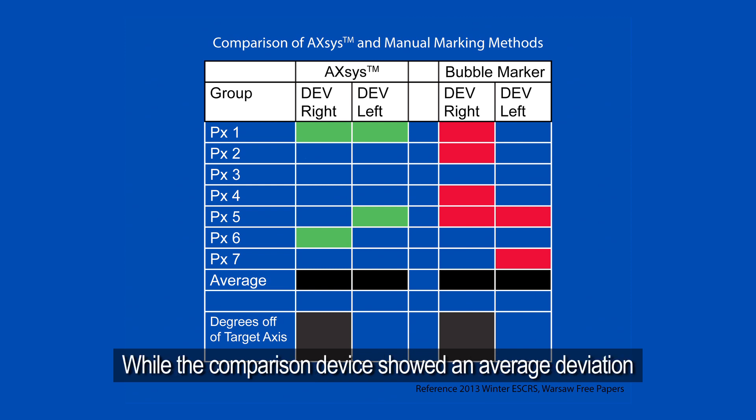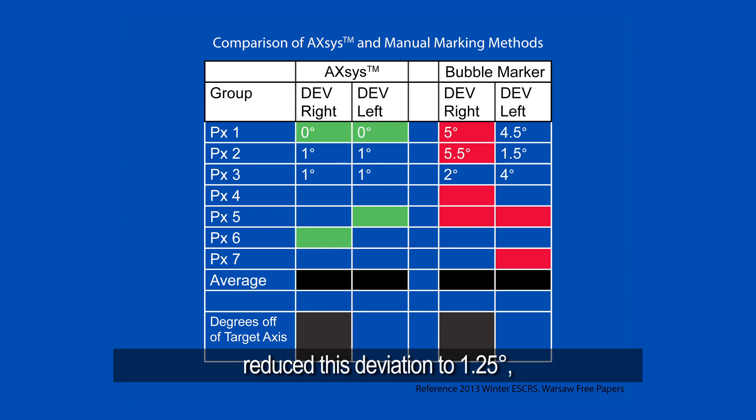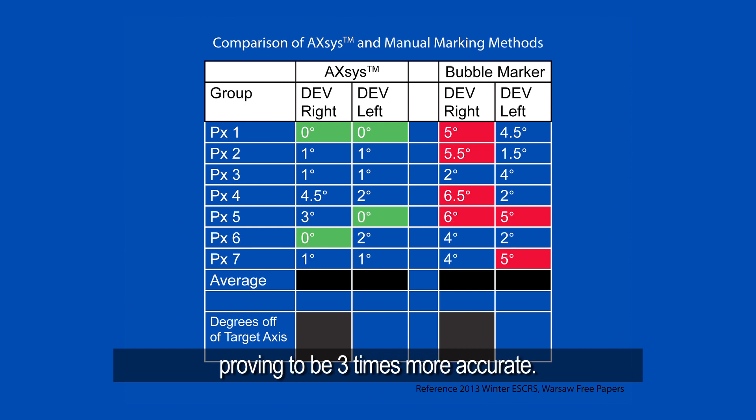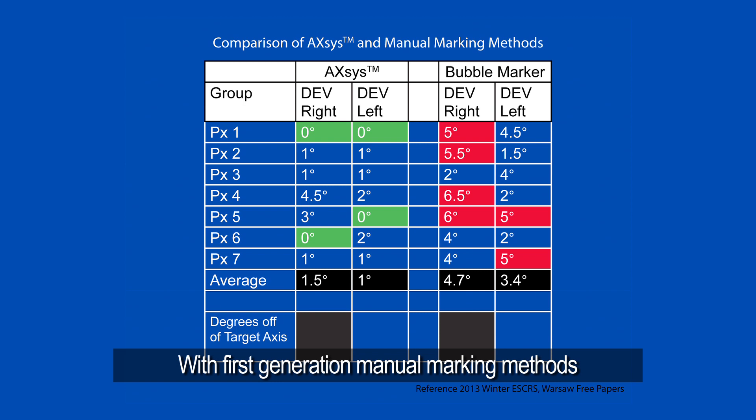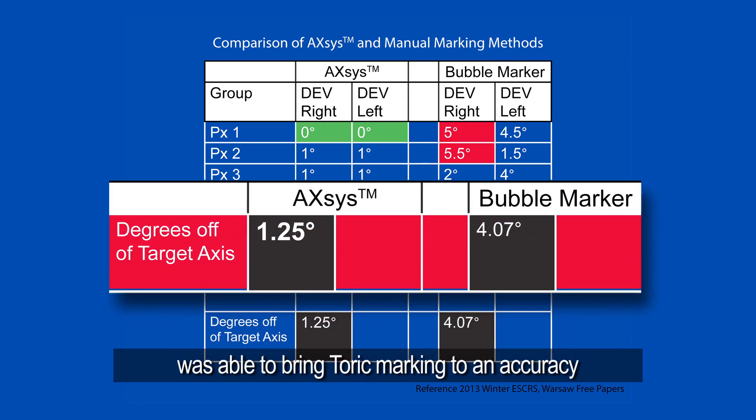While the comparison device showed an average deviation of 4.1 degrees, the AXsys electronic toric marking device reduced this deviation to 1.25 degrees, proving to be three times more accurate. With first-generation manual marking methods yielding an average misalignment of over 5 degrees, the AXsys electronic toric marking device was able to bring toric marking to an accuracy that could not be achieved before.